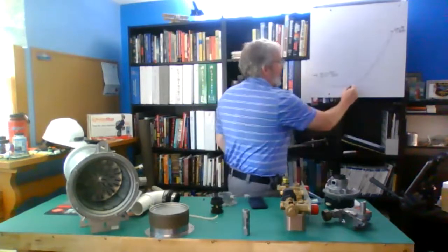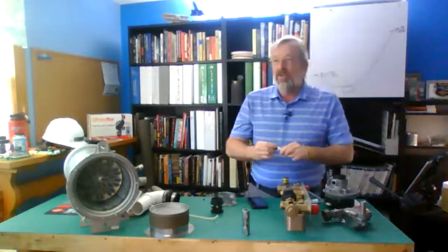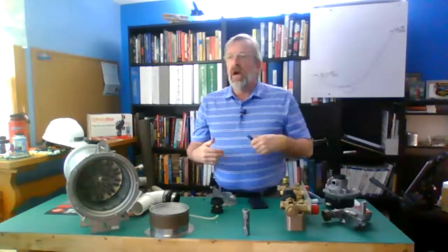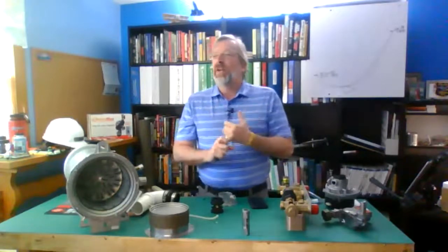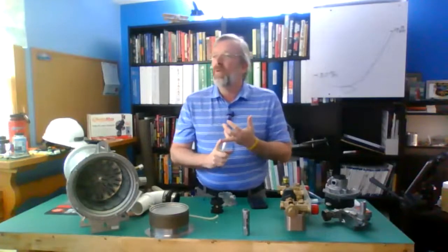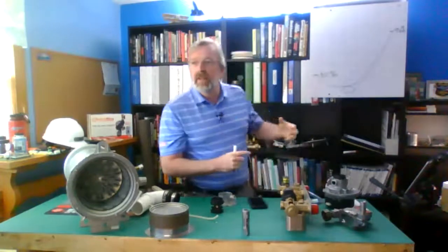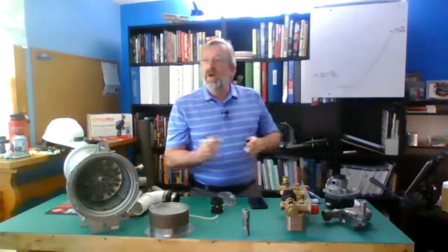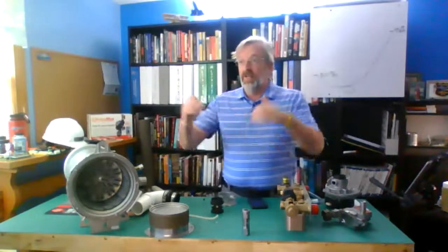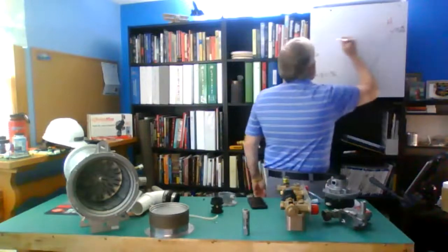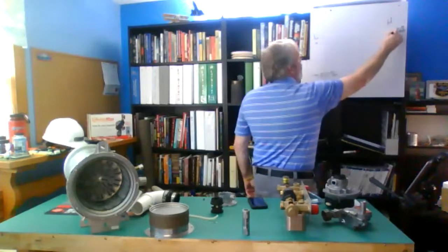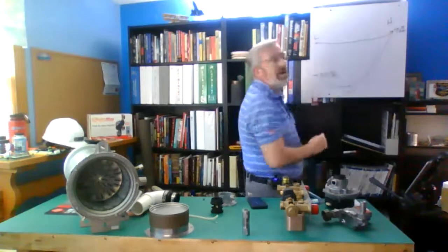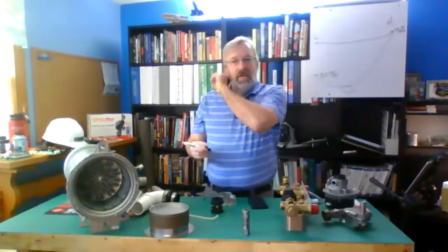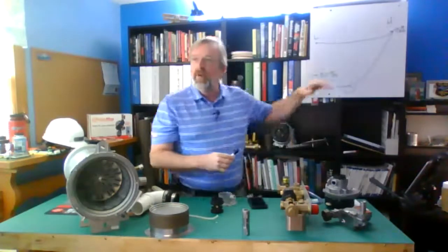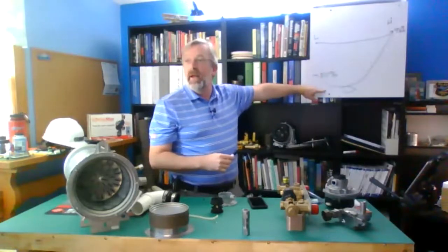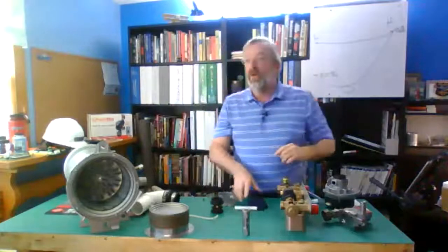And this shows up as hard starts. Your customers' complaint is going to be my boiler stutters when it starts. I get frequent or infrequent flame failures. It's something along those lines. So that's why we say when you set up, not caring where your numbers are, as long as they're in that range, that high fire and low fire, when they're closer together, it looks like that when I'm ramping. And I know it's hard to see those numbers, but the numbers aren't as important as getting them close together to prevent that from happening. And that's that droop. That's what we're looking for. And that's why we want them close together.